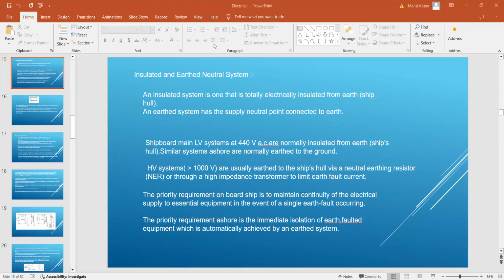For the ship, you can understand that if there is a single earth fault, the machinery will still run. For the high voltage system, why are we using the neutral earthing system? Why not this, 440? Yes, this is what you should ask me, right? In the high voltage ship, why are we using the earthing system? Why are we not using the insulated one?